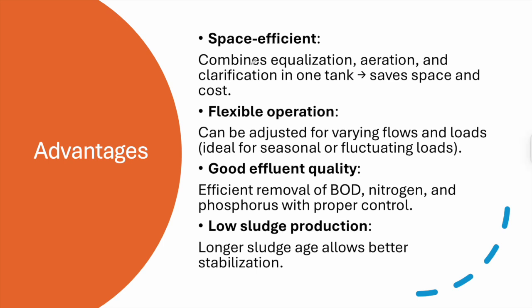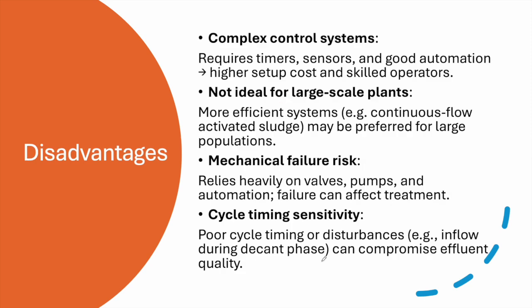The advantages of SBR include space efficiency — equalization, aeration, and clarification all occur in one reactor, saving space and cost compared to traditional activated sludge processes. It offers flexible operation, adjustable for varying flows and seasonal or fluctuating loads. It achieves good effluent quality with efficient BOD, nitrogen, and phosphorus removal with proper control. It also produces low sludge due to longer sludge age, allowing better stabilization.